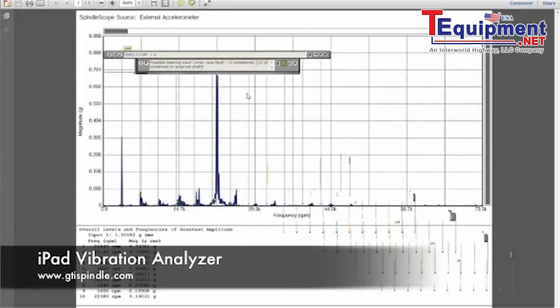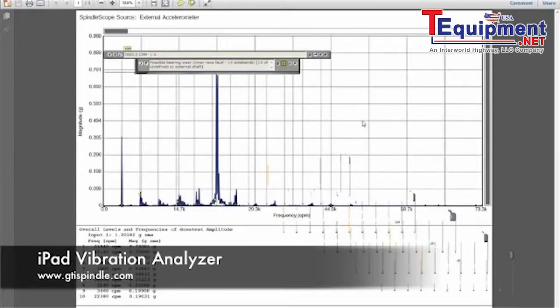Here it says 'possible bearing wear,' and I know this to be true because I know the motor I measured. Here's the running speed, and the high peaks occur at many multiples of the running speed. In this case, the interpreter is correct.